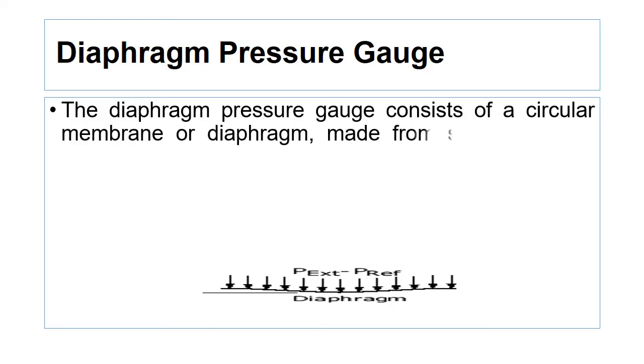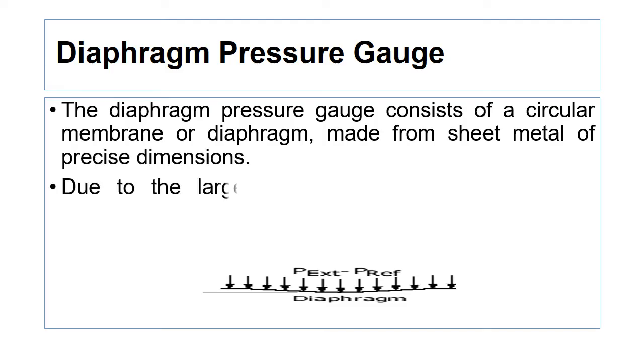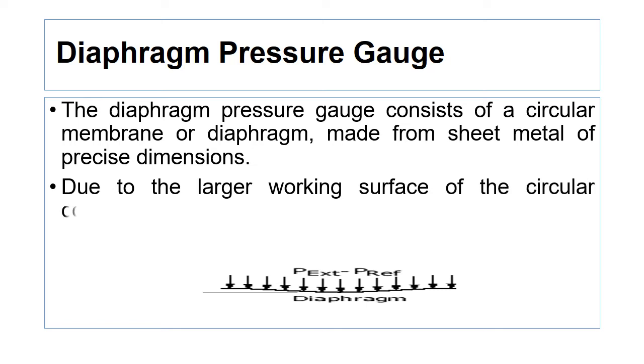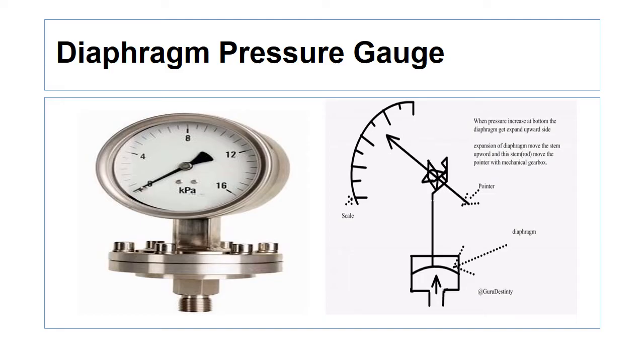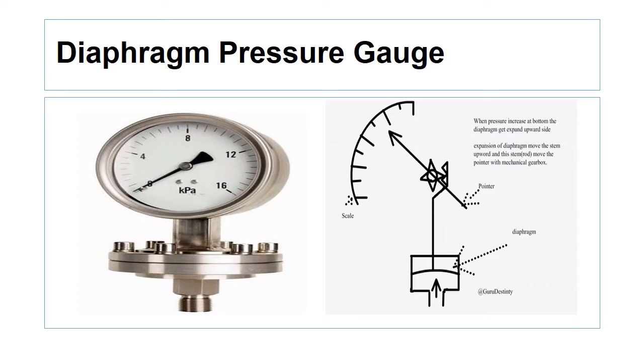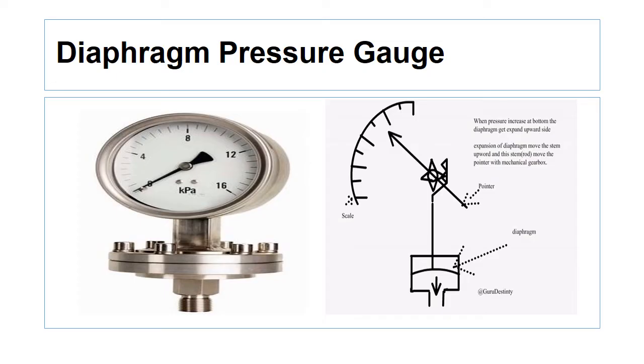Due to the larger working surface of the circular corrugated diaphragm element, small pressures can be measured accurately. The diaphragm is mechanically connected to a transmission mechanism which can amplify the small deflections of the diaphragm and transfer them to the pointer. The lower side of the diaphragm is open to the pressure to be measured, while the upper side is at atmospheric pressure.